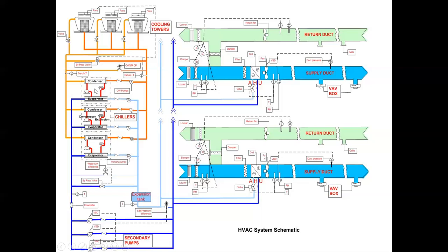It goes to the dorms. It goes everywhere, and so it's going to pick up some heat. It goes through the pumps, and the pumping energy heats it up a little bit, and the insulation's not perfect, so it's probably going to be 44, 45 before it gets to Brown Hall and some of these other places. There's our return water coming back from the building. Return water is going to come back 52, 54, something like that.